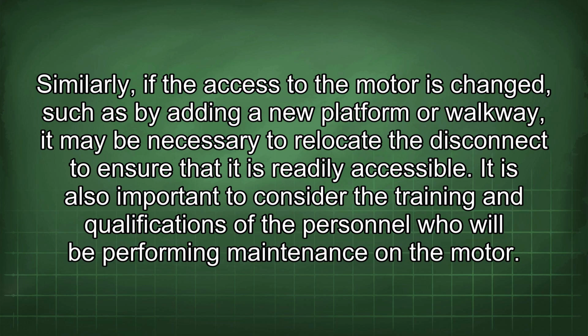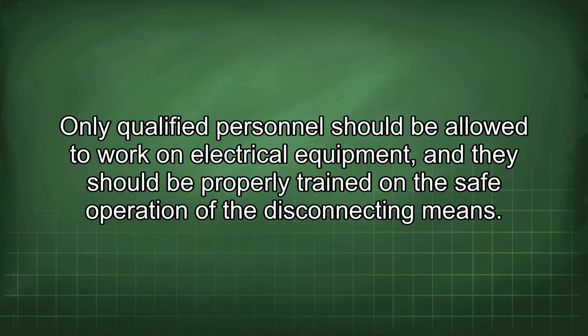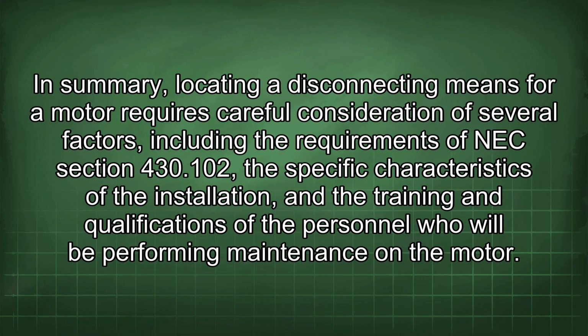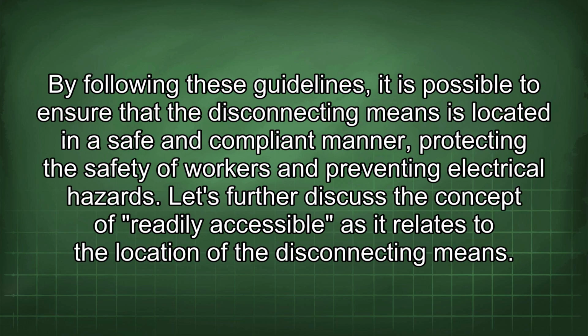It is also important to consider the training and qualifications of the personnel who will be performing maintenance on the motor. Only qualified personnel should be allowed to work on electrical equipment, and they should be properly trained in the safe operation of the disconnecting means. In summary, locating a disconnecting means for a motor requires careful consideration of several factors, including the requirements of NEC section 430.102, the specific characteristics of the installation, and the training and qualifications of the personnel who will be performing maintenance on the motor. By following these guidelines, it is possible to ensure that the disconnecting means is located in a safe and compliant manner, protecting the safety of workers and preventing electrical hazards.